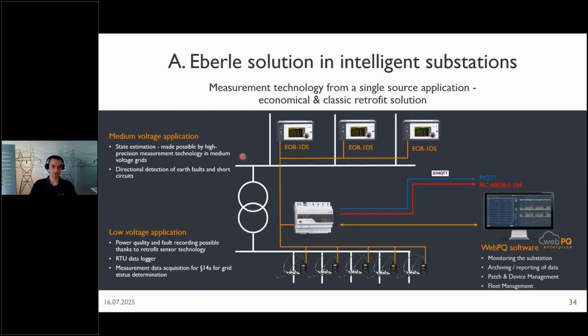So you have state estimation that is made possible by high precision measurement technology in these medium voltage grids. And of course, also directional detection and indication of earth fault with the EOR-1DS. And then on the low voltage side, you have the PQI-LV that has power quality and fault recording possible, also with the retrofit sensor technology. It has an RTU data logger and measurement data acquisition.